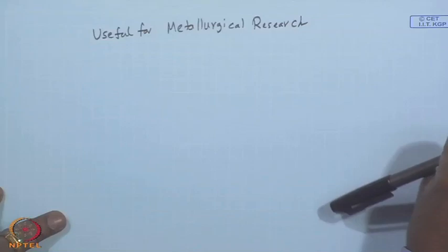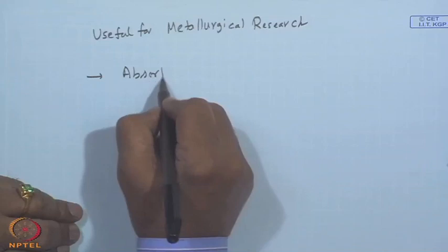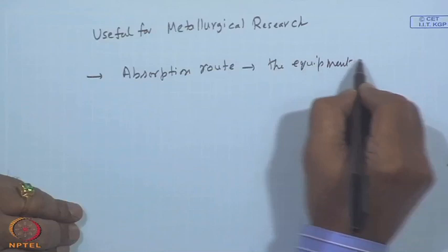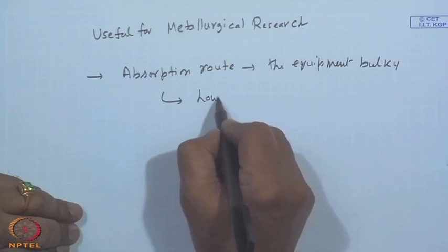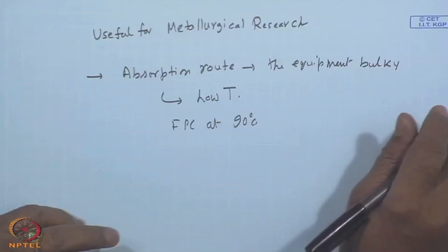And air conditioning and refrigeration has not met so far perhaps that much success. One is if you go through the absorption route, the equipment is bulky. Essentially, I mean low temperature. So, something like maybe a flat plate collector at 90 degrees C supplies energy at about 90 degrees C. So, consequently, your COP will be pretty poor.